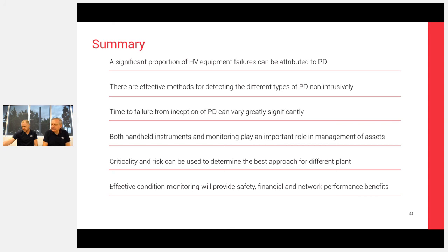How often does the Astute need to be calibrated for its accuracy? Again, an interesting question. Formally, we often calibrate things every 2 years for an installed monitor, or we do a check on that. The system itself does automatic checking on this. And there's another fundamental question. Some people don't actually go for a calibration once they've installed a monitor. You know if it's working or not. It has got its auto checking.